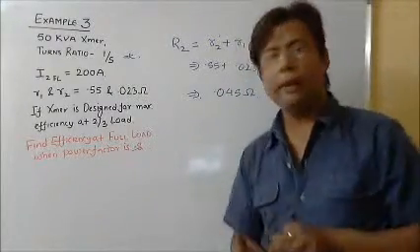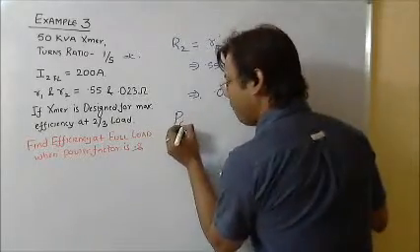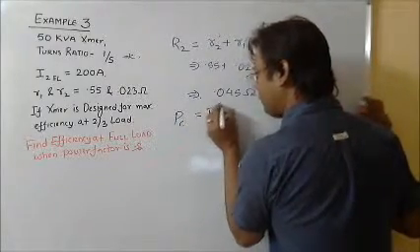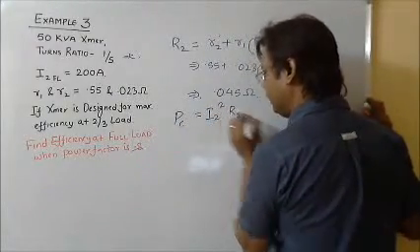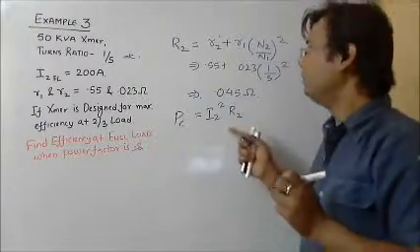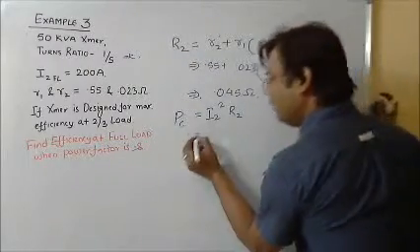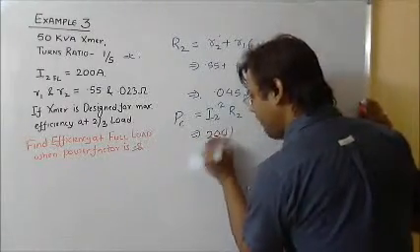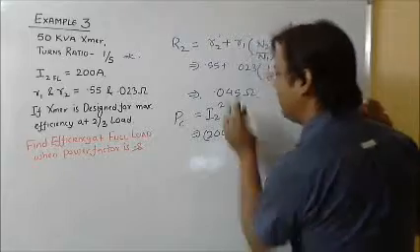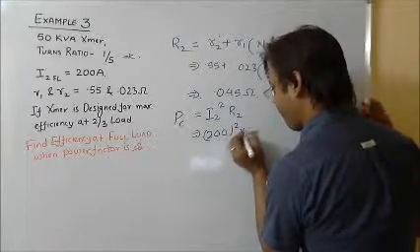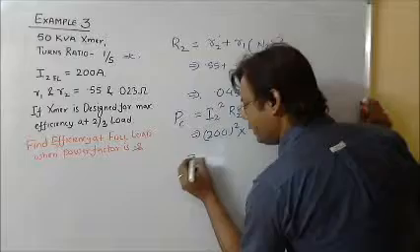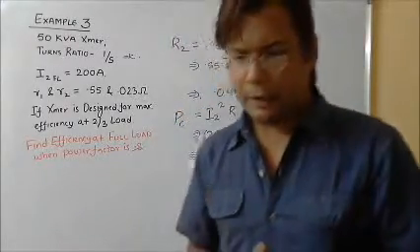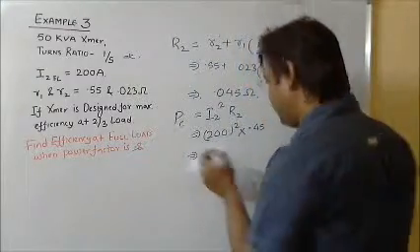So now I can find Pc total copper loss, which is equivalent to I2 square R2 dash. I know secondary full load current is 200 amperes, so that is 200 squared multiplied by 0.045, which comes out to be 1800 watts.